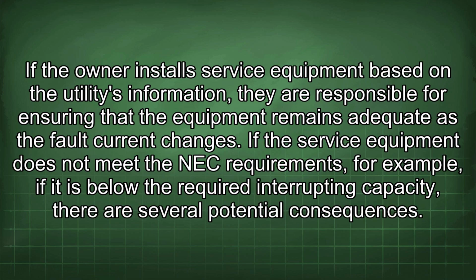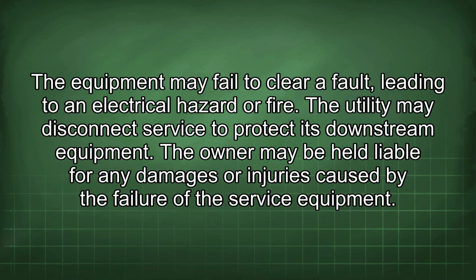If the owner installs service equipment based on the utility's information, they are responsible for ensuring that the equipment remains adequate as the fault current changes. If the service equipment does not meet the NEC requirements, for example, if it is below the required interrupting capacity, there are several potential consequences. The equipment may fail to clear a fault, leading to an electrical hazard or fire. The utility may disconnect service to protect its downstream equipment. The owner may be held liable for any damages or injuries caused by the failure of the service equipment.